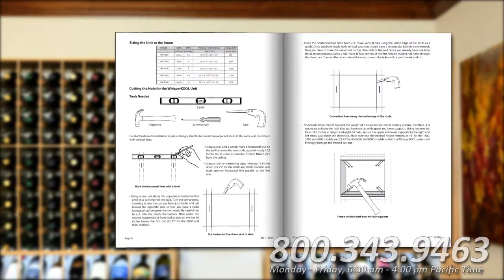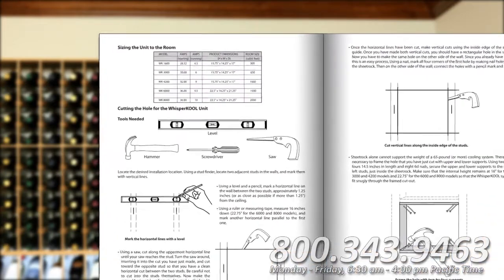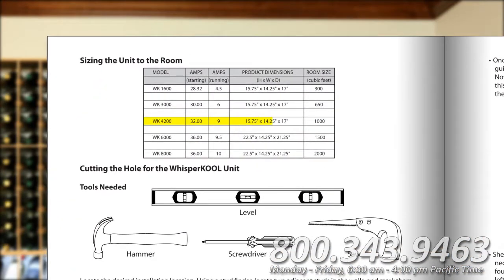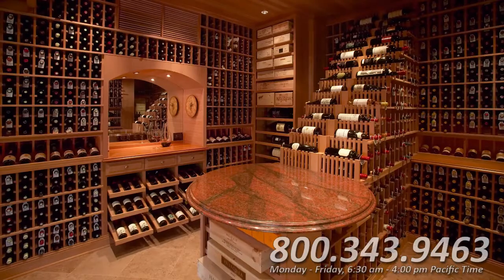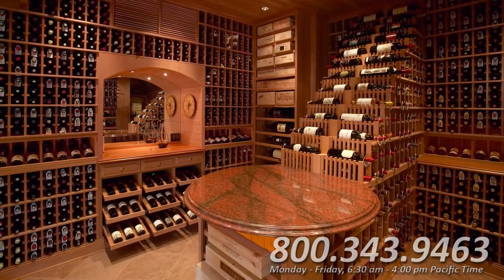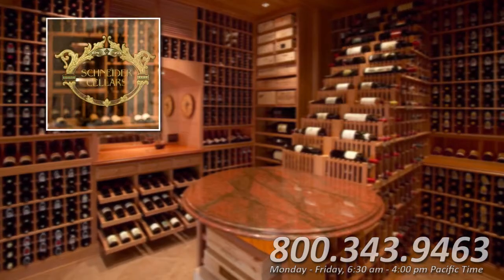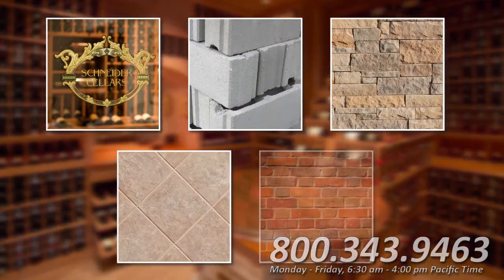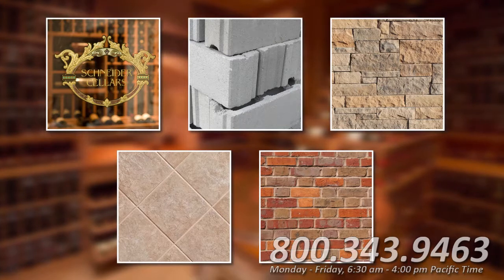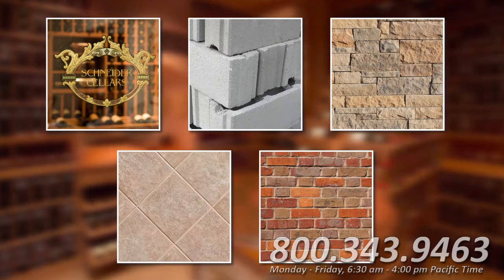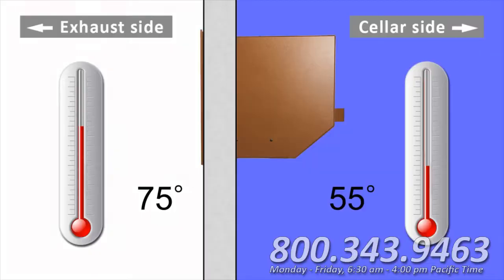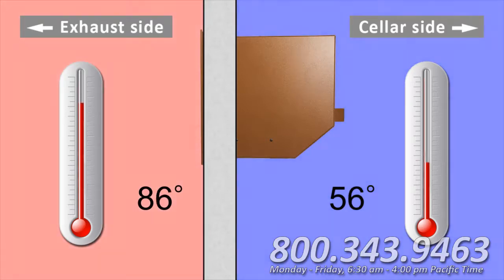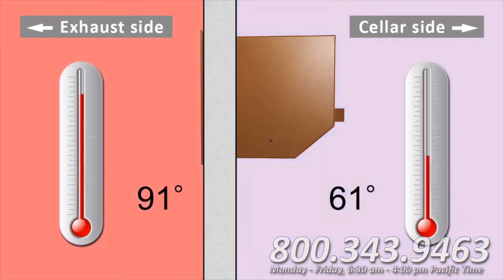Also, check the owner's manual to make sure that your cooling unit is rated to cool the number of cubic feet in your cellar. If your cellar is larger than the unit specifications will allow, you need to upgrade your unit. Even if your cubic footage is within the specs, remember that building materials like glass, cement, stone, tile, brick, and others will absorb the cool air or transfer heat from the outside to create an additional draw on the cooling unit. And if the intake air temperature from the exhaust room rises above 85 degrees, the unit will not be able to cool to 55 degrees because it only cools 30 degrees cooler than the intake air.